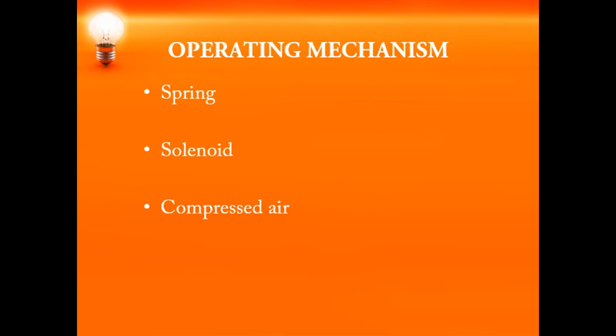We know that when a circuit breaker is going to operate on a fault, the contacts have to get separated. That means the moving contact has to move away from the fixed contact, is it not? So when this moving contact has to get separated from the fixed contact, there should be some mechanism which is trying to pull the moving contact. That pulling of the moving contact can be either due to spring, solenoid or compressed air.